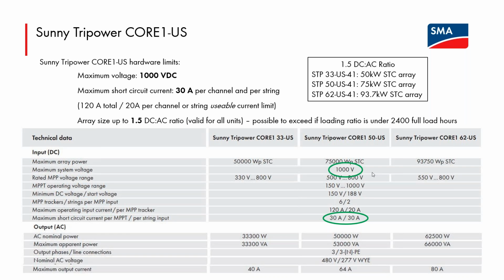So they want the inverters to be working at full power for as many hours as possible every day to maximize the value of the plant, even though they face a certain AC kilowatt or megawatt connection power limit. So they can't add more inverter capacity, but potentially they can add more array capacity.